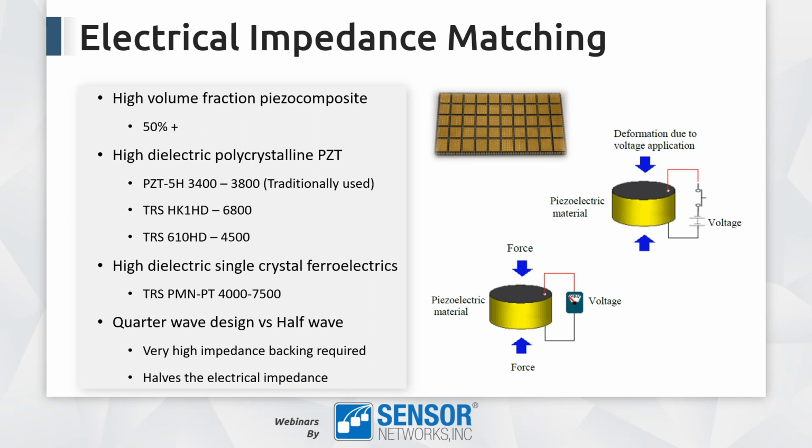We can also look at different materials. Traditionally, PZT5H materials are widely used in phased array transducers, for medical and for industrial. But there are several newer materials available that have higher dielectric constants. A couple are listed there.